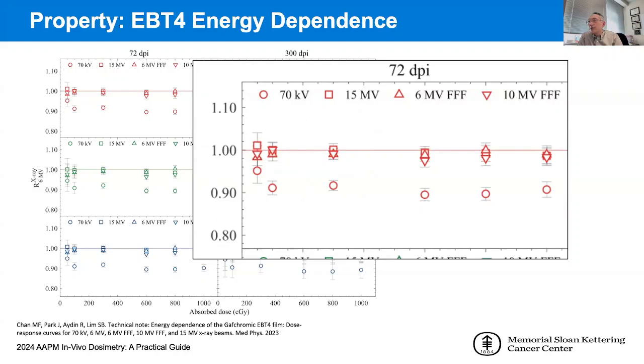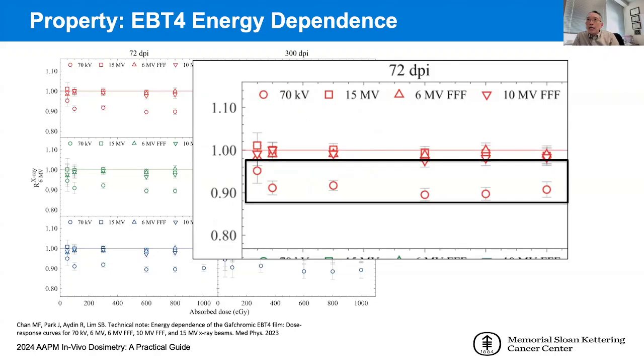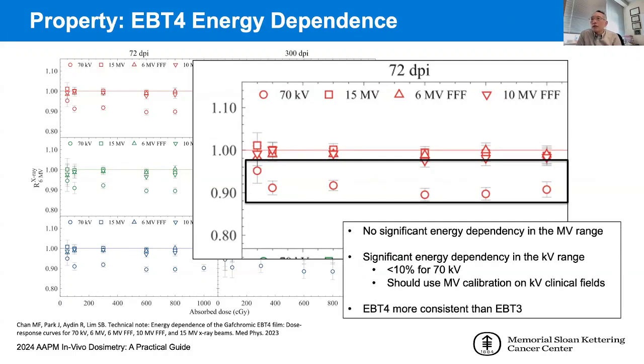Ranging in energy from 15 MV, 6 MV FFF, and 10 FFF. In the MV region, they all have a pretty similar response, meaning that you probably can use a single calibration curve for all the MV beams. But what we notice here in the lower energy, in the superficial orthovoltage range, is a significant energy response compared to 6 MV. So what it means is that when we look into the lower energy range, if we want to do in vivo dosimetry, we should consider using a calibration curve in the kV range. And we should not use an MV calibration for that, to avoid introducing a systematic error.